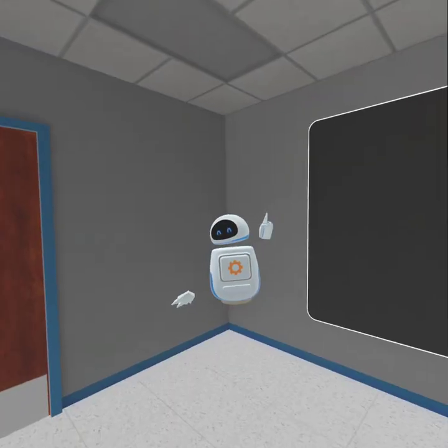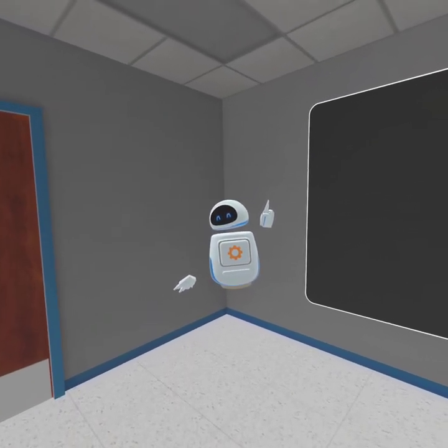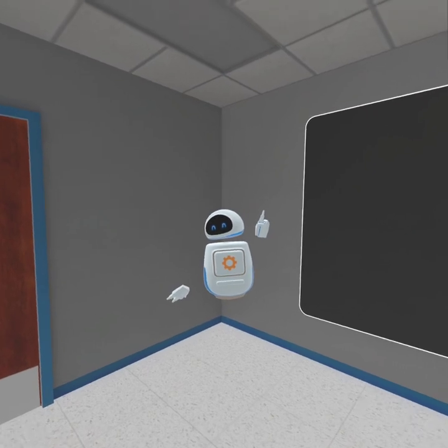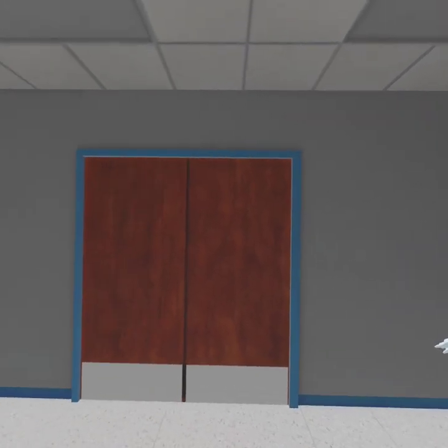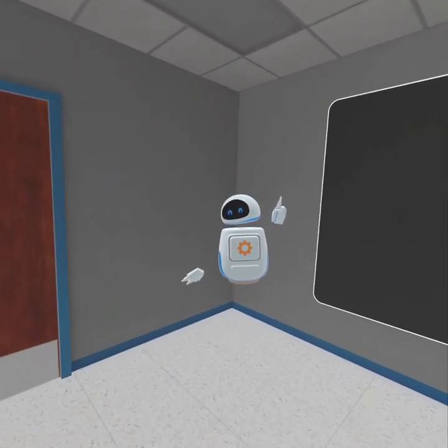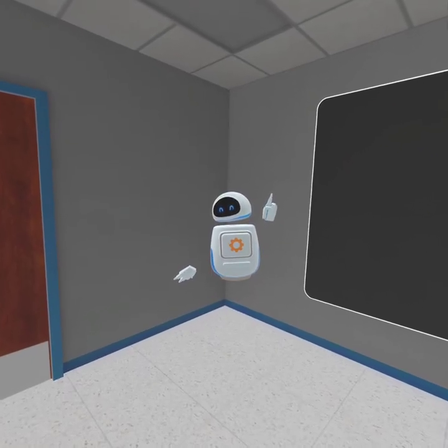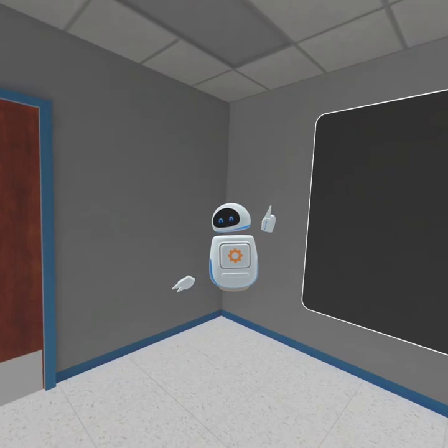Good job. Let's learn more about it. In cone beam and fan beam CT, geometric magnification happens when the object is positioned closer to the X-ray source and farther from the detector. This increases the size of the projected image, but can also introduce geometric distortion, blurring, or cone beam artifacts because of the angular divergence of the X-ray beam.